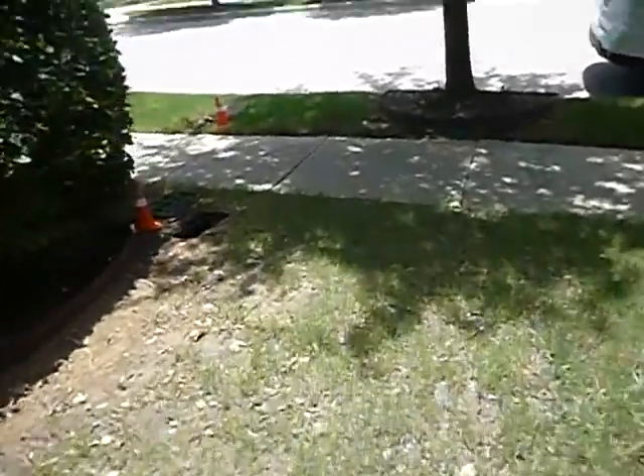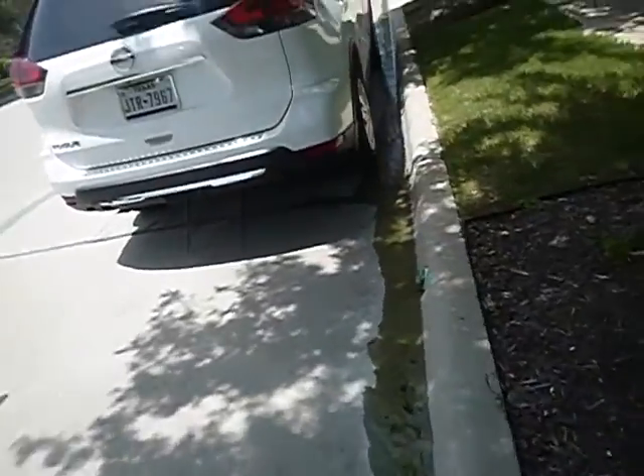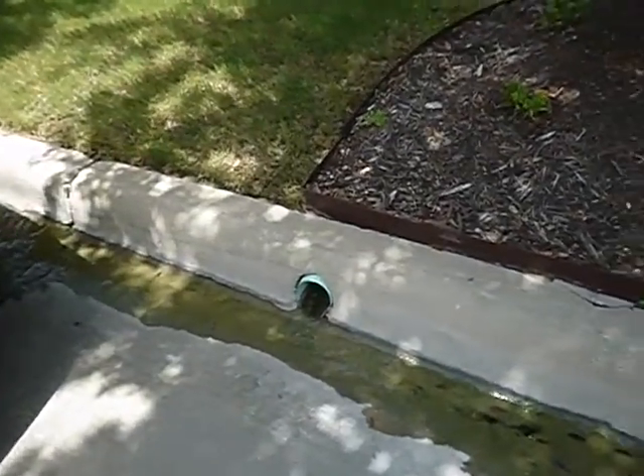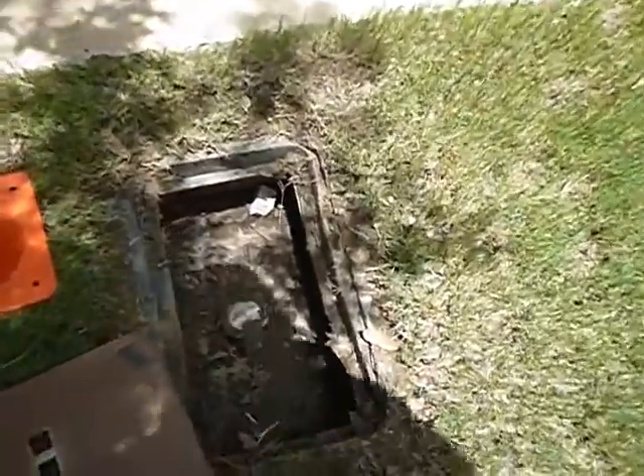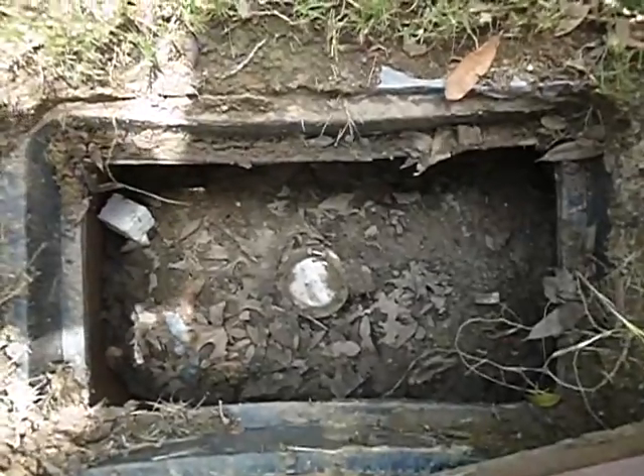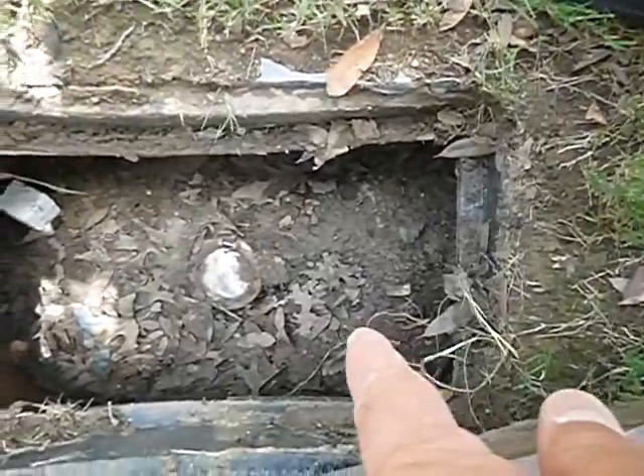But we come along here. I can't really show you, but this is where the sump pump discharges. There's a short video I've done about that already. This is the water meter to the home, and this box should be excavated so that you can get around and you can turn the water off. There's the valve right there. Inside this irrigation box, that little chrome and black sprocket in the center is called a flow indicator switch. Some people call them cheater wheels or cheater paddles. And if that's moving, then fresh water is moving into the structure.